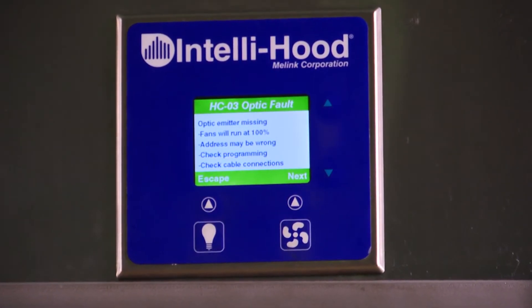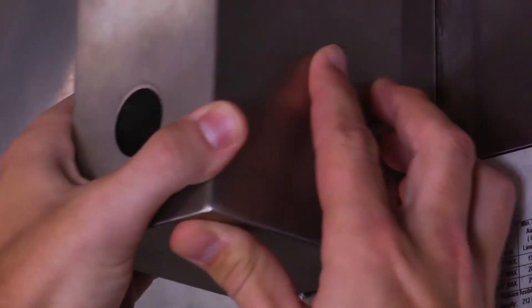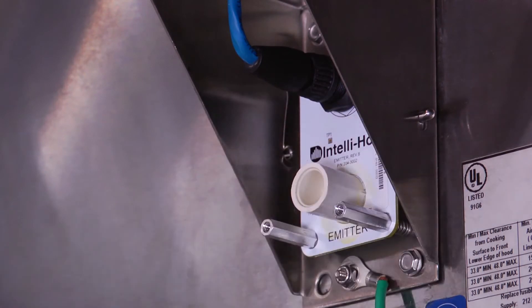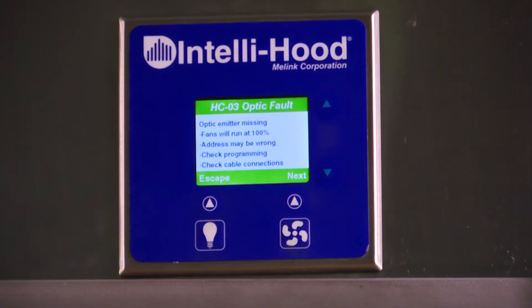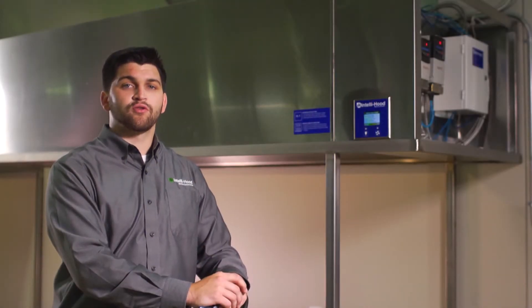First, we'll cover clearing an optics fault. Melink recommends cleaning your optics a few times each month. If there's a large amount of buildup on the lens or a simple obstruction in the hood, the touchpad will show an optic fault. An optic fault will cause the hood fans to run at full speed until the fault is cleared, allowing you to continue cooking while preventing you from saving energy.